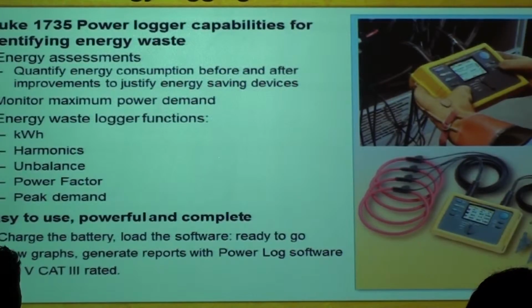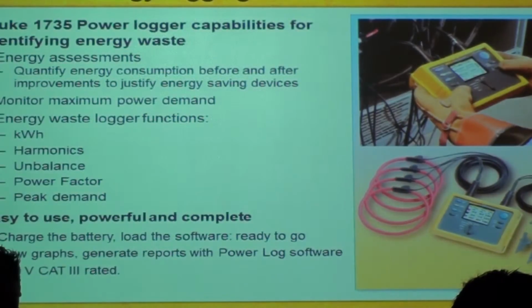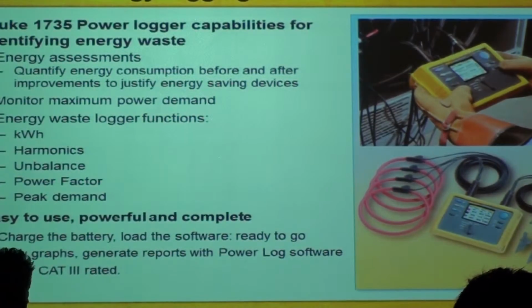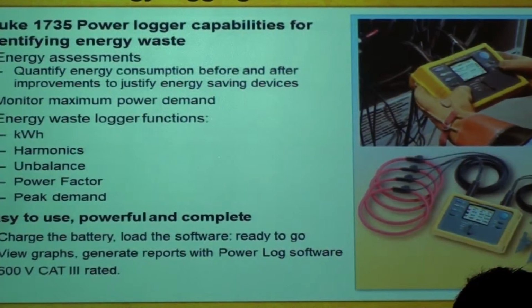And when the power comes in and goes to the loads, let's say the branch circuits, so fixed loads like elevators and motors, the connections there, that's a category 3 area, where you also have a problem. And then it branches down to, let's say, electrical sockets, receptacles, all these plug points. These are category 2 installations. And then if I open up my laptop and I work on the printed circuit board, that's a category 1 installation. Where I can have a fault, I can have a spark or whatever, but the energy produced is not high enough that it might kill you. It might cause you a burn. It doesn't kill you really, okay?